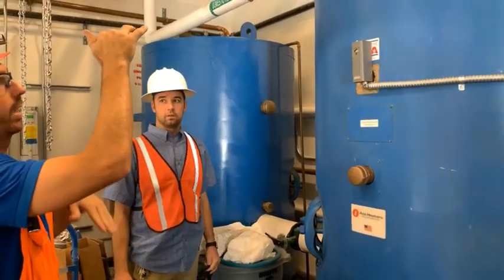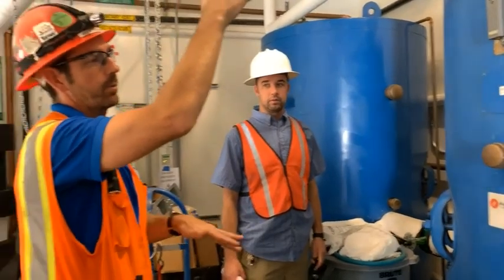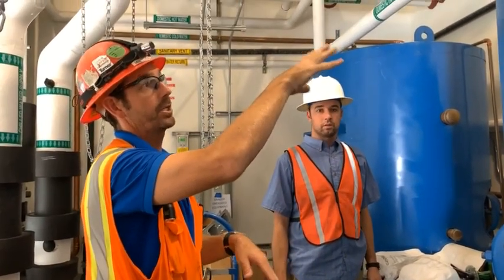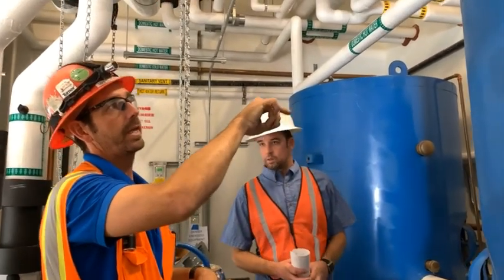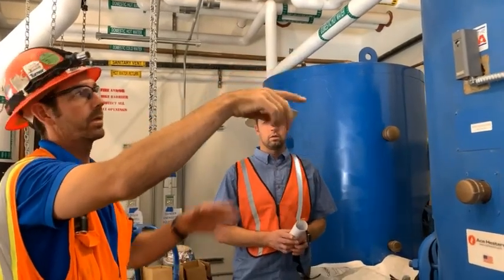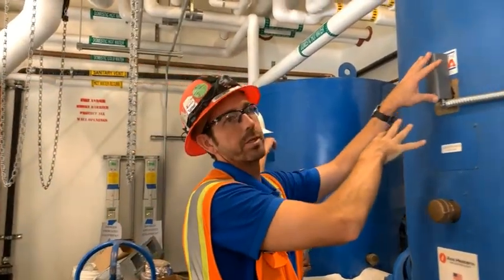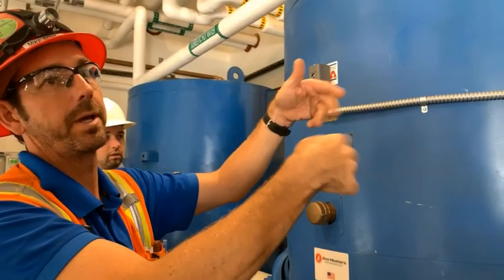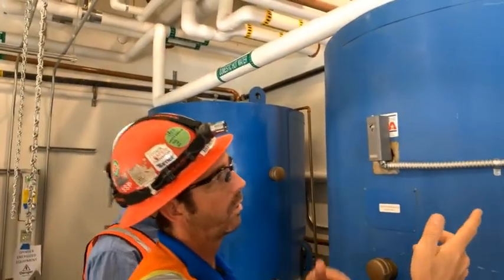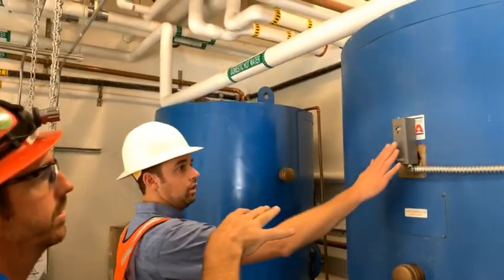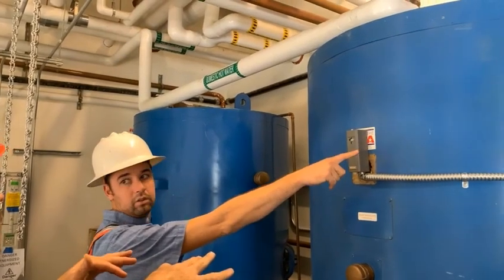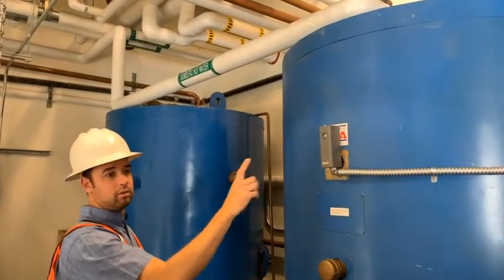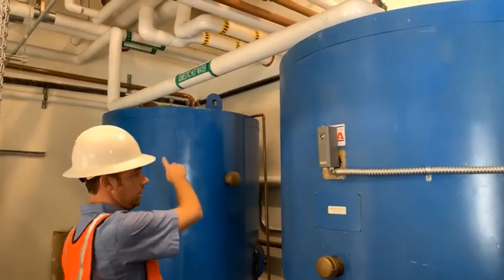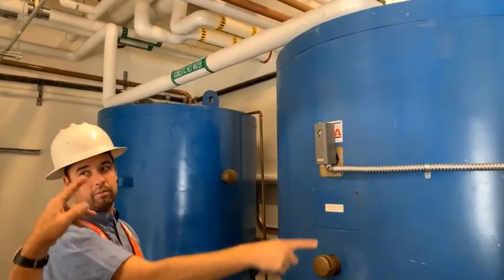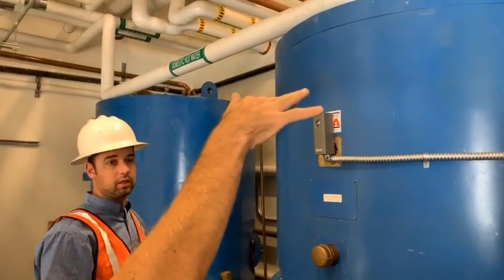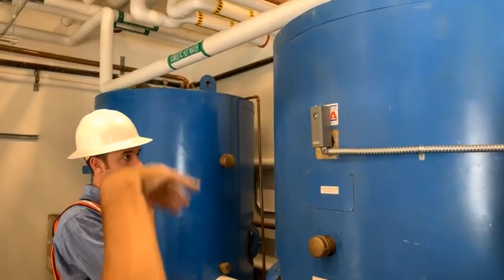And if you're isolating one tank, make sure that you isolate that pump. Because if you drain this tank and it cools off, it will try to turn on a pump, and then there's no water for it. Each tank goes to one pump. One tank is designated to one pump, and this tank is designated to the other pump. The left tank is the top. It's like you read top to bottom, left to right.